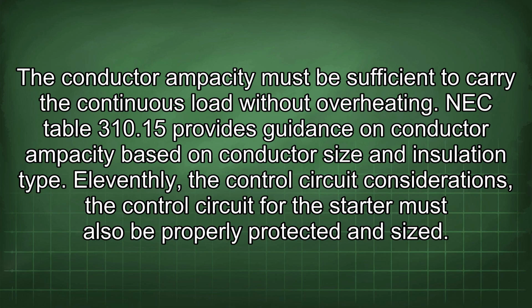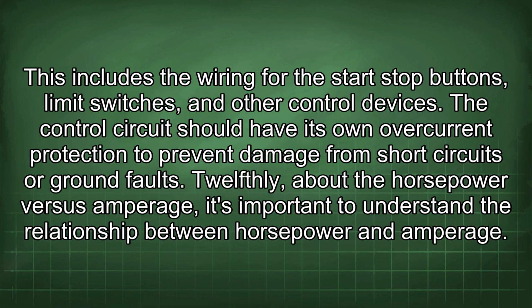11thly, the control circuit considerations. The control circuit for the starter must also be properly protected and sized. This includes the wiring for the start-stop buttons, limit switches, and other control devices. The control circuit should have its own overcurrent protection to prevent damage from short circuits or ground faults.